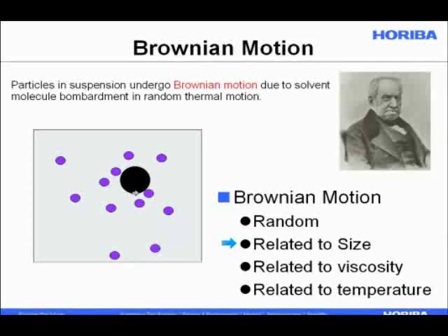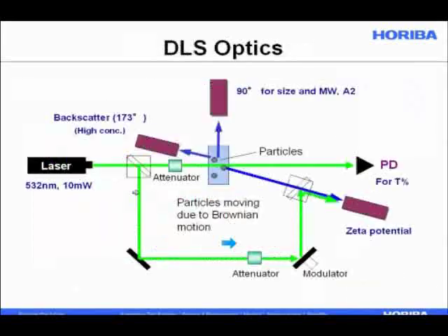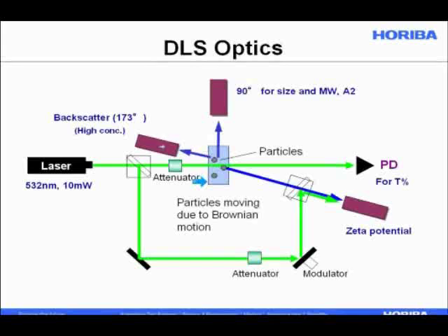Let's talk about the optical arrangement. This is a top view of an optical plate on, say, the SZ100 or any other dynamic light scattering instrument. You have a laser light source shining a focused beam onto the particle sample, and then we look at it from the side, back, or front with detectors — measuring the intensity of light scattered at, say, a 90-degree angle. An extra optical path is used when making a zeta potential measurement or finding electrophoretic mobility.